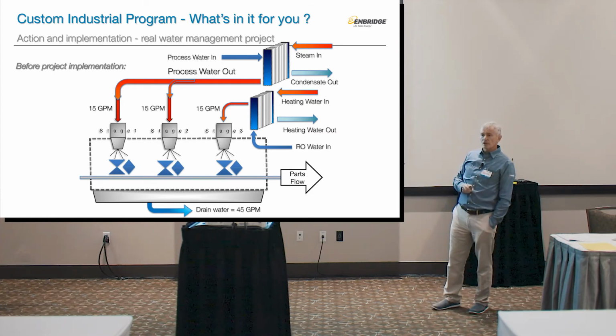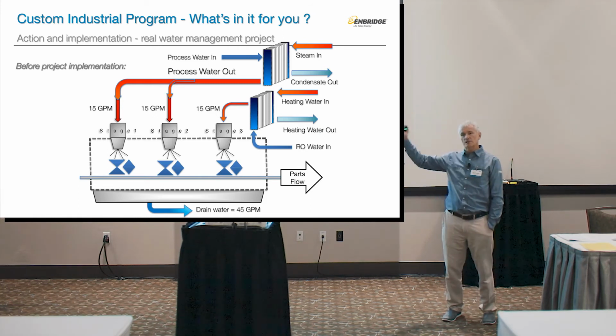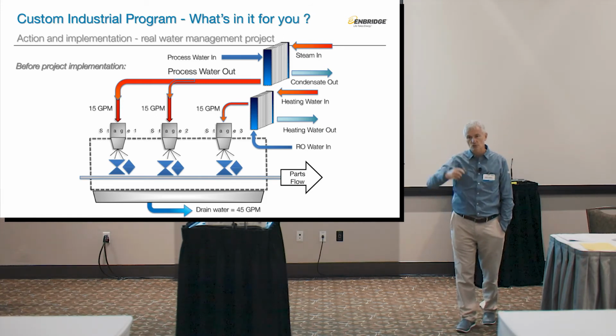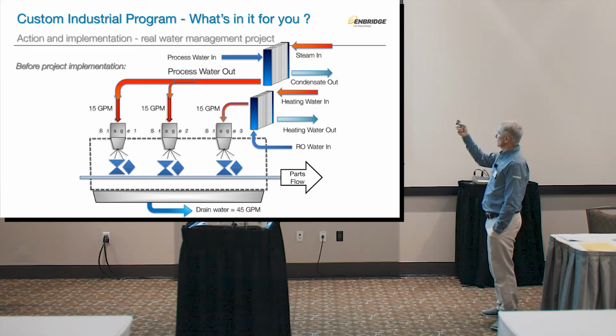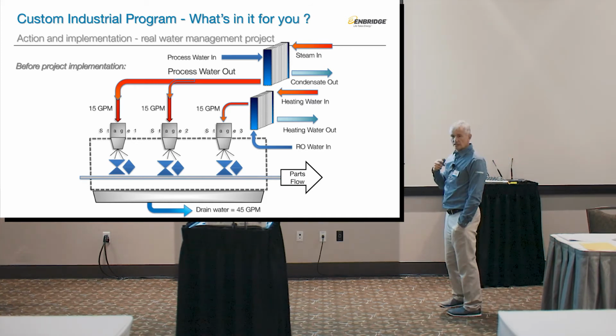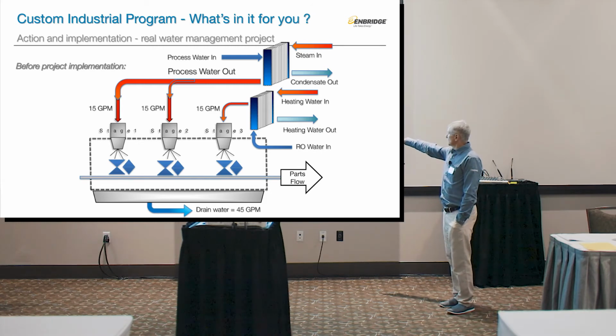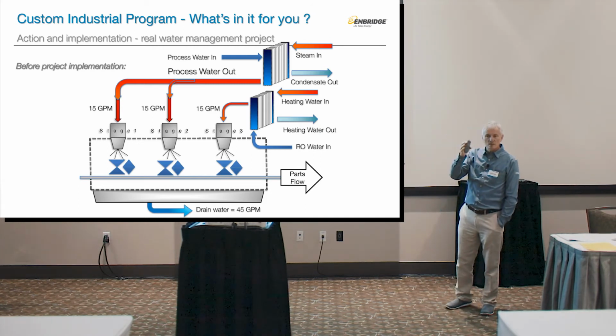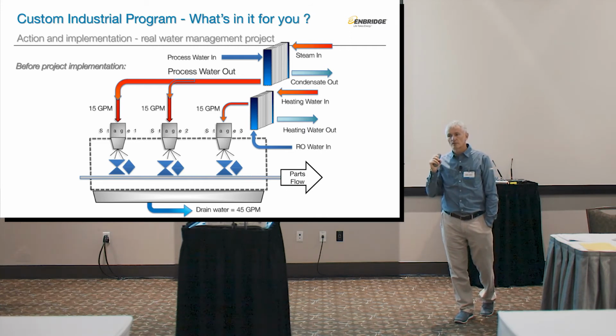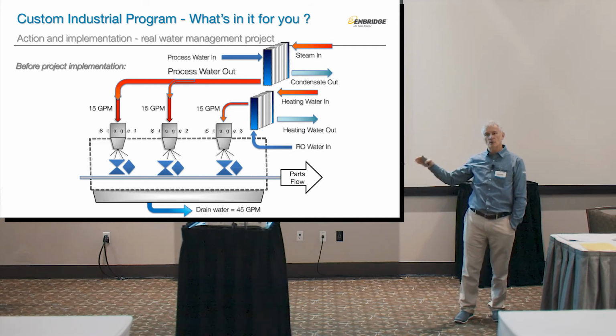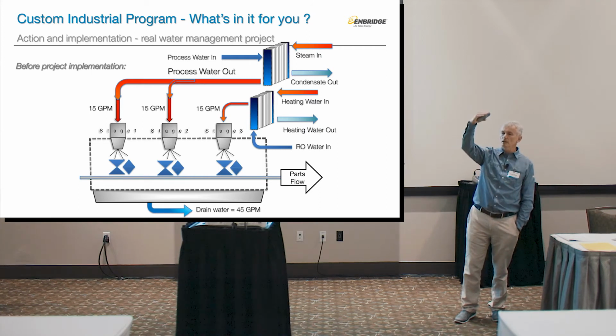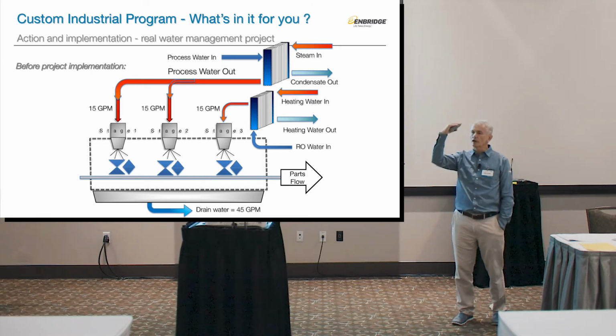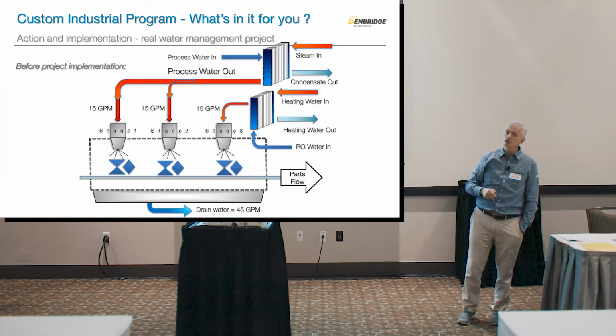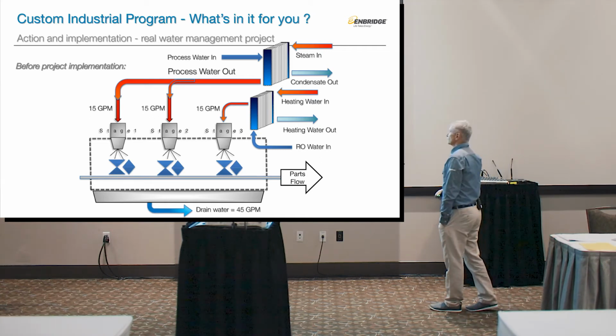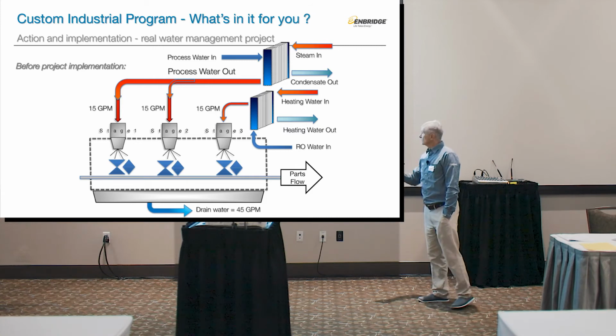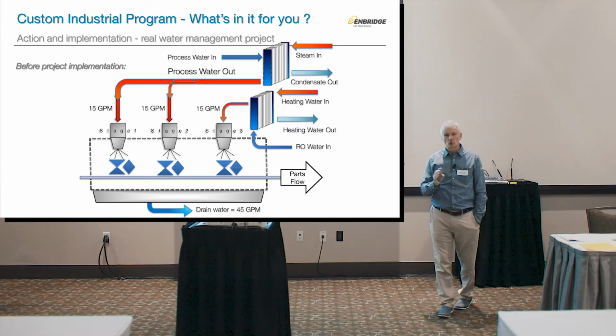We put a natural gas water heater in there. Instead of using steam from the central plant, we put a natural gas water heater next to the unit. So now we are at 92% efficient heating, and we only bump up a little bit. This water actually loses maybe 30, 40 degrees F. So instead of draining it and then heating the water from 50 degrees F to 180, now we just go from 130 to 180 every time. And we don't use city water anymore as much. And then we'll drain just a little bit, this 5 GPM that we need to drain to make sure that everything's clean.